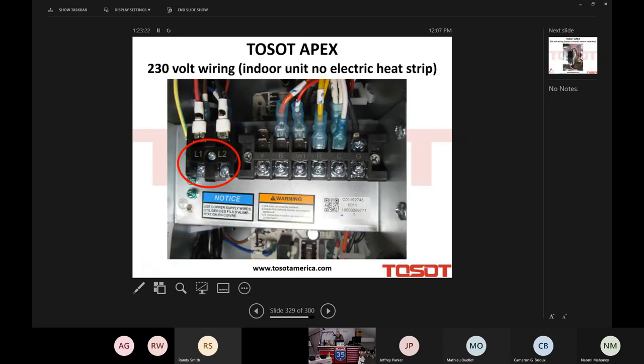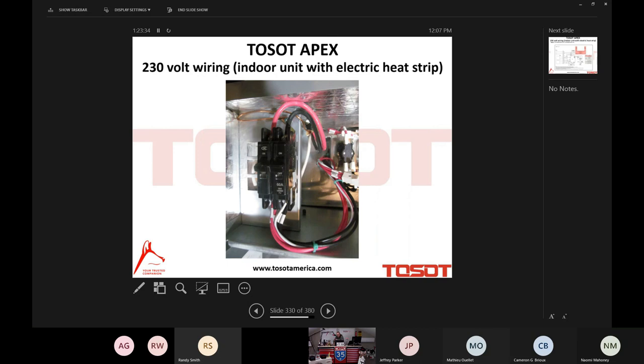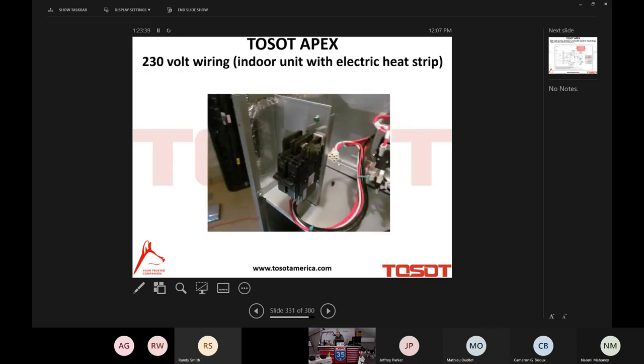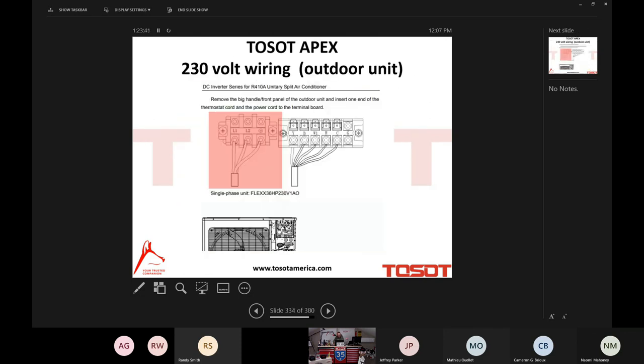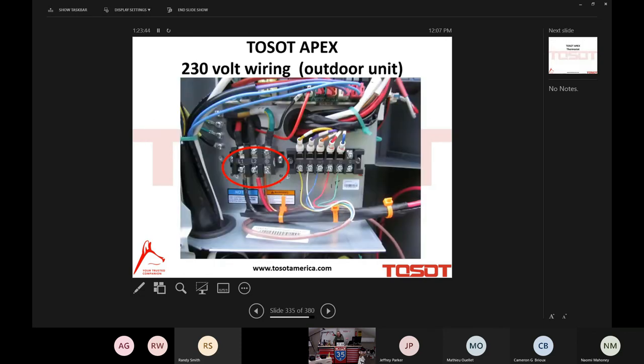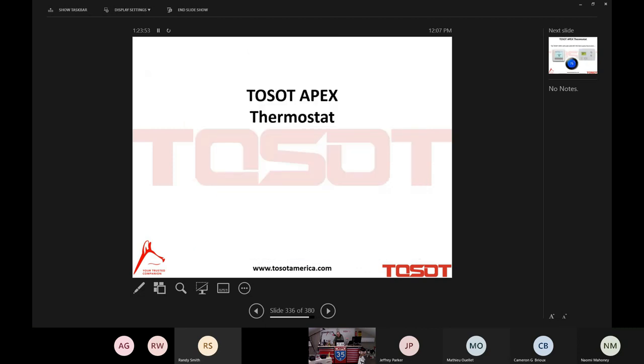There's your L1, L2 of the indoor unit. Again, we're only bringing our source power to L1 and L2 of the indoor unit if we are not using the electric strip. If we are using the electric strip, we're bringing power to the breaker provided with the electric strip, whether it's one or two breakers. And there is our power to the outdoor unit, L1, L2, and ground. That's our 208, 230 volt power source to the outdoor unit.